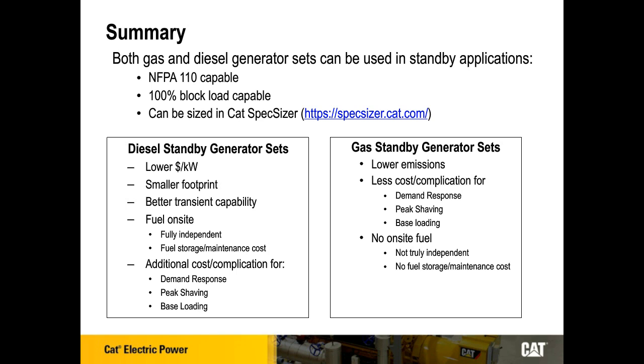On the natural gas side, it has lower emissions, so for demand response, peak shaving, and base loading, there is significantly less cost and complication, making gas the better choice in most of those applications. It also does not have on-site fuel, so on the negative side it's not truly independent, but you also don't have the fuel storage and maintenance costs that you do on the diesel side.